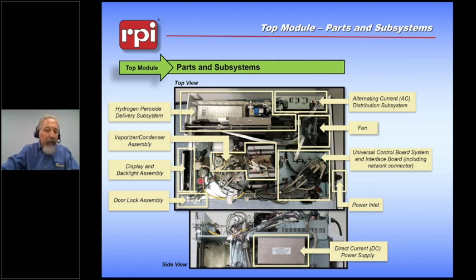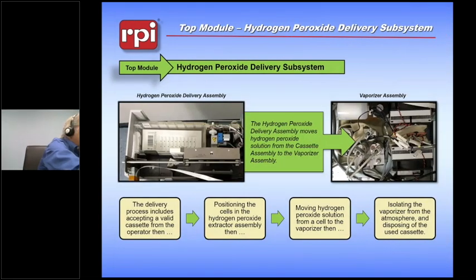We have our pressure transducers. We have a UV light, a monitoring system, a way to keep the door closed. Of course, a cartridge system and a way to get the hydrogen peroxide out of the cartridge. And then down here on the side, we have our DC power supply to supply DC power to the CPU and the I/O cards. On the back of the machine itself, that's where the power cord comes in, and there's also a data card for all the runs that sticks out the back here. It's not quite shown. Okay, so we're going to break those sections down.